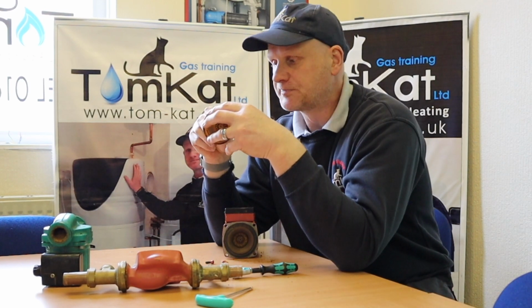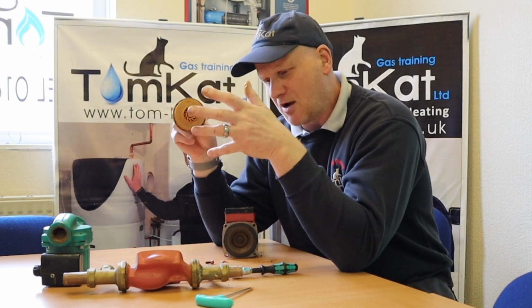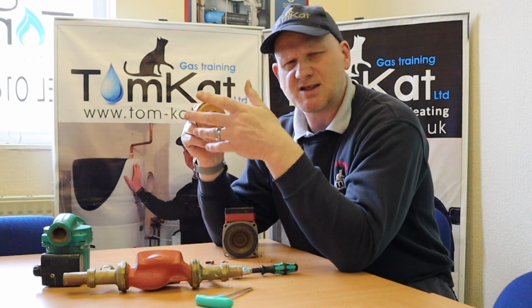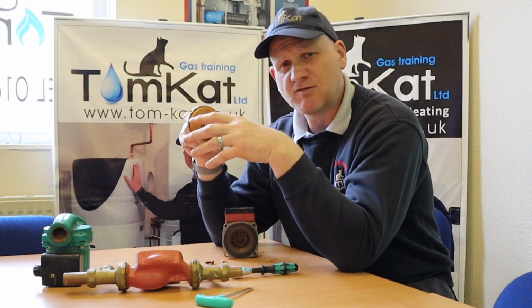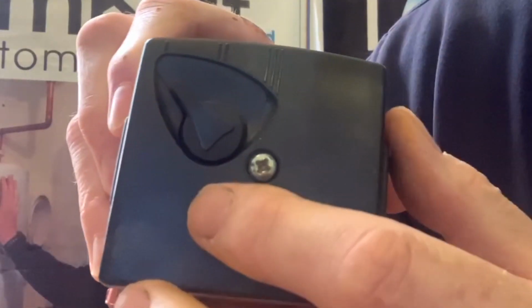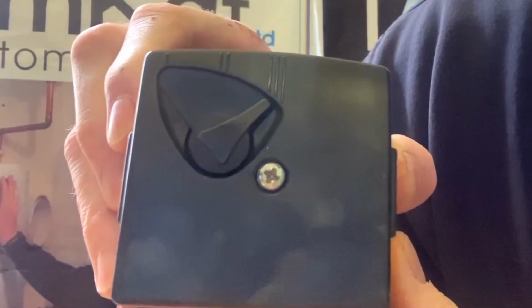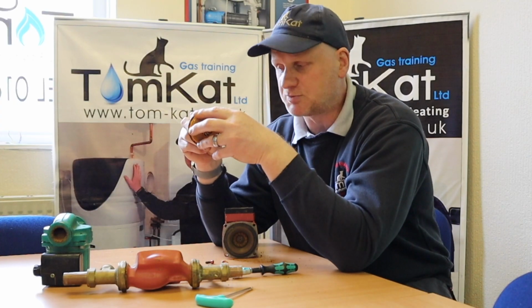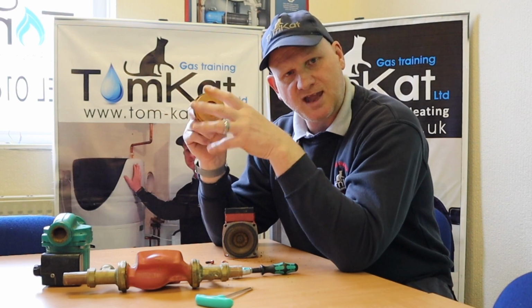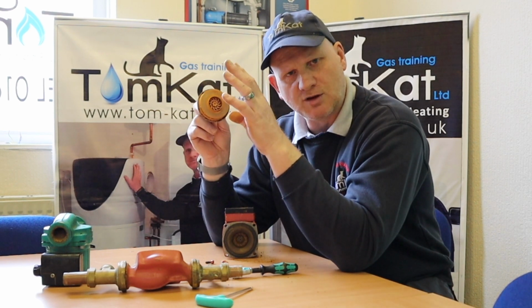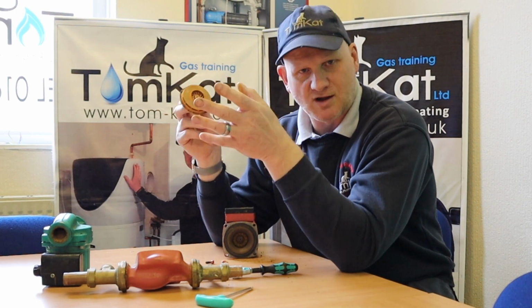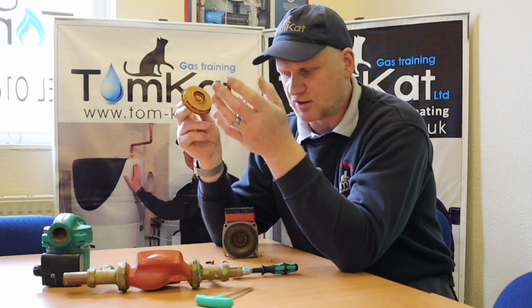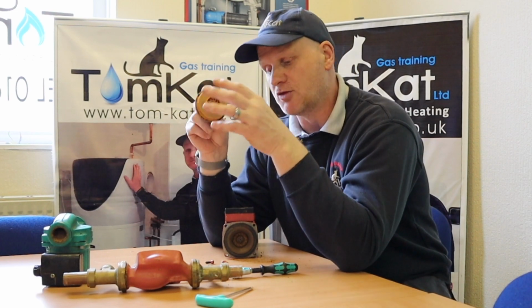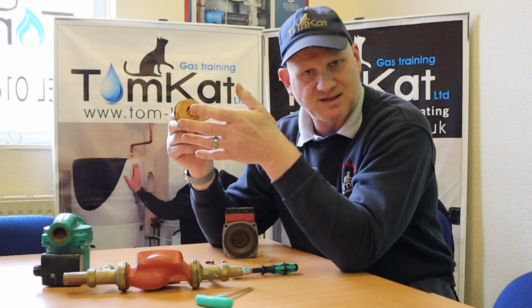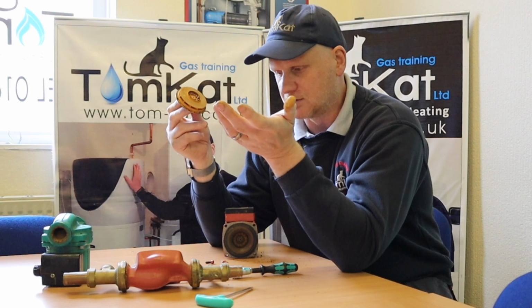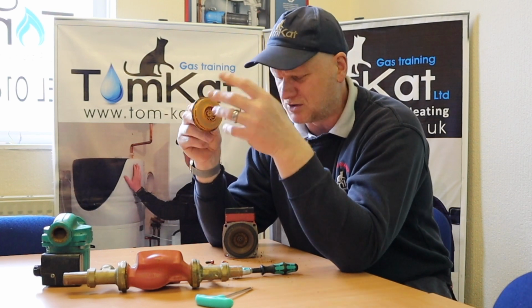Now, a lot of pumps come with 3 speeds, but the 3 speeds is really the pressure. If you've got a small system, you should have it on a low speed or low pressure, and if you've got a big system, then you should have it on a fast speed or a large pressure. If you've got a really noisy heating system, that could mean that the water's going through the radiators that quick. One, it's not efficient, and two, it's making this horrible noise. So you can actually adjust them. On the new ERP pumps, they automatically adjust the flow rate to reduce the pressure, but we'll look at those later.